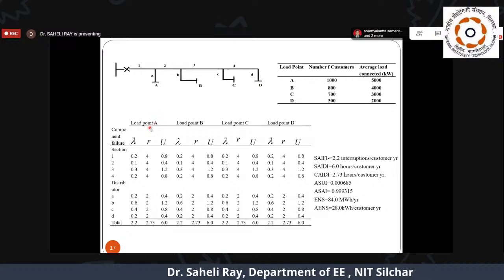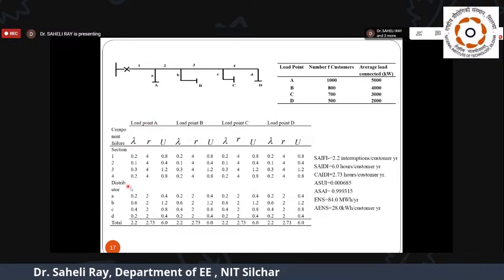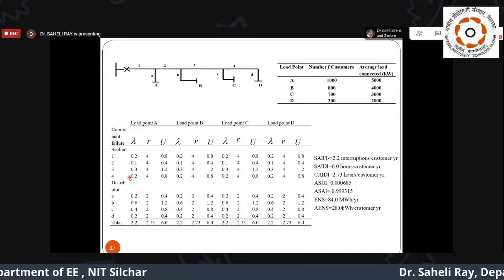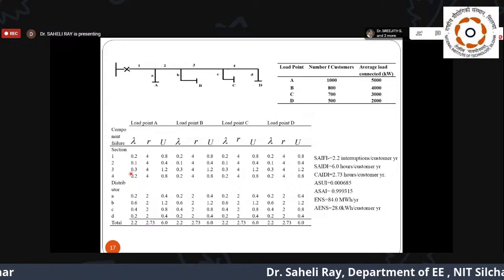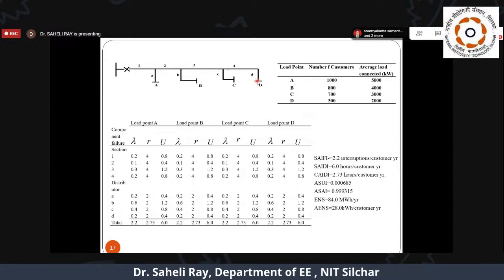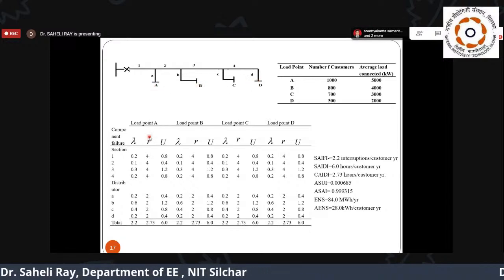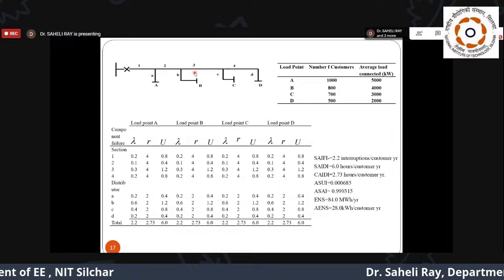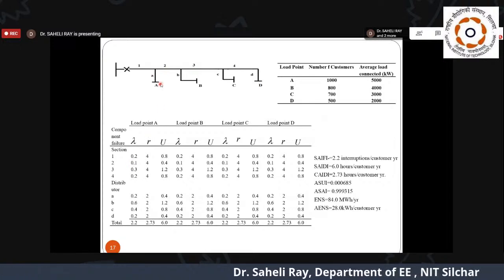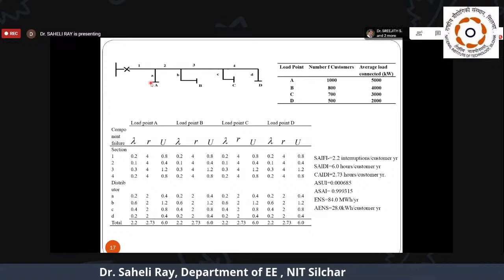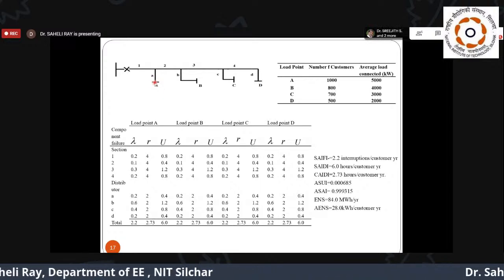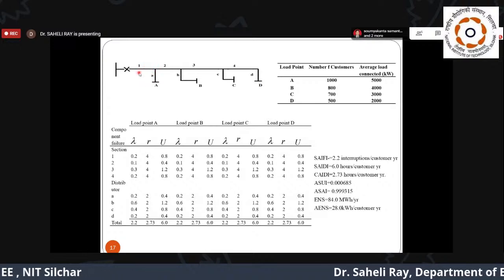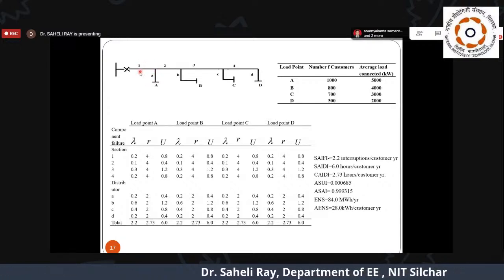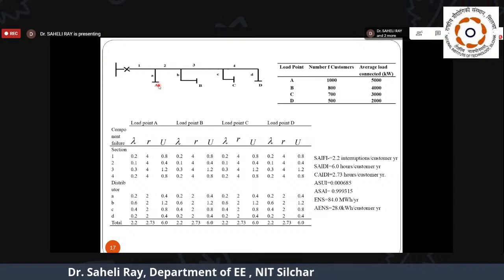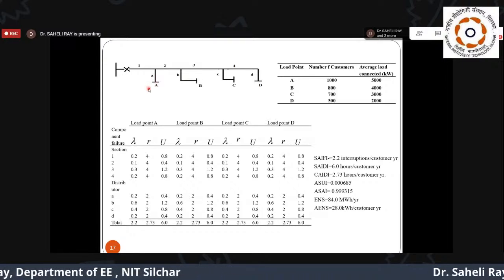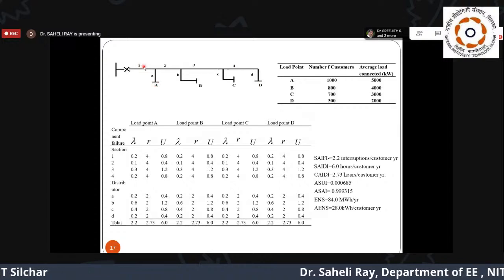Now again, we have the section-wise data, per kilometer fault. So we need to find the load point data: load points A, B, C, and D. Let us concentrate on this diagram. If a fault occurs, concentrating on load point A, what will be the failure rate of load point A? If a fault occurs at this segment, then what will happen? Load point A will be disconnected and we will not be able to restore power to this load point until the fault is repaired.